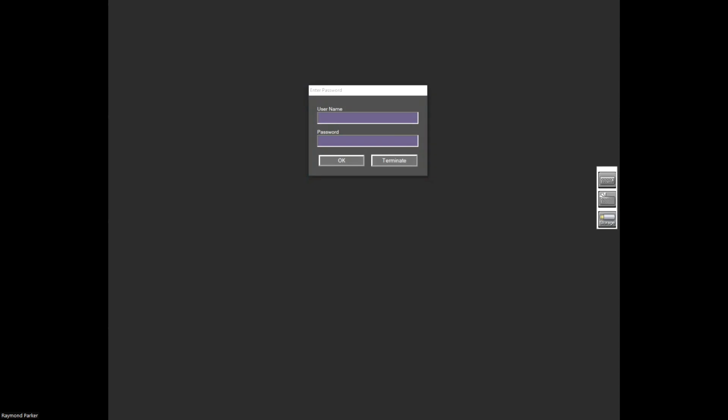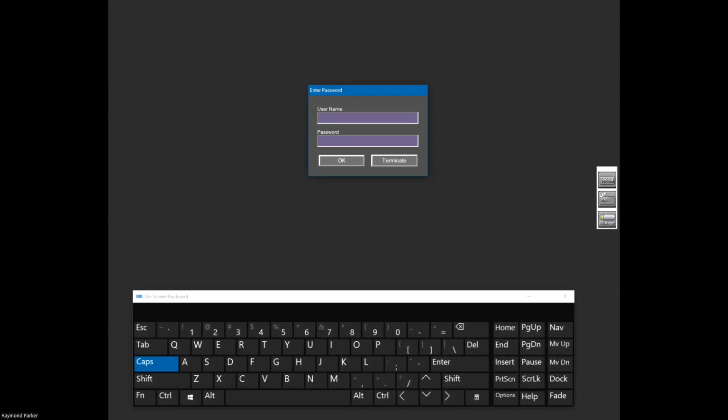When you've turned on security as a function, you'll have to, on the first time in, use our service password for end user name, which is capital F, capital F, capital S, and then a lowercase ER, VICE. So it's capital F, F, S, and then all lowercase ERVICE.